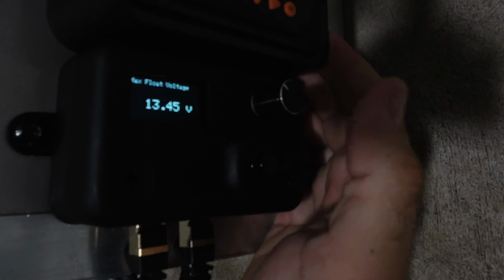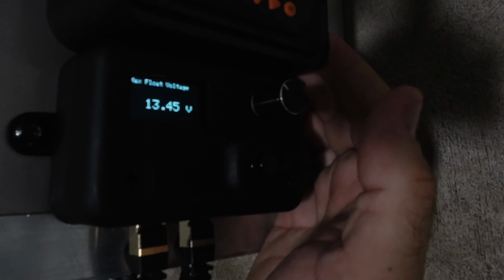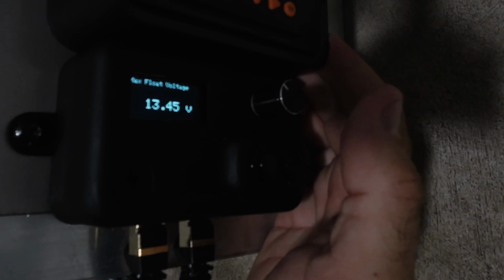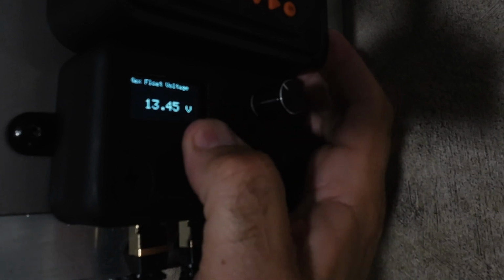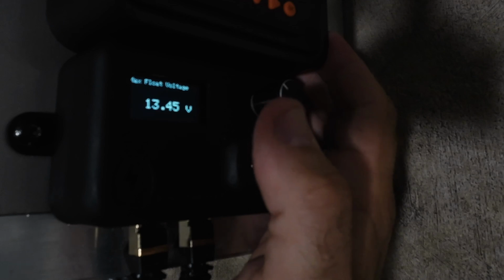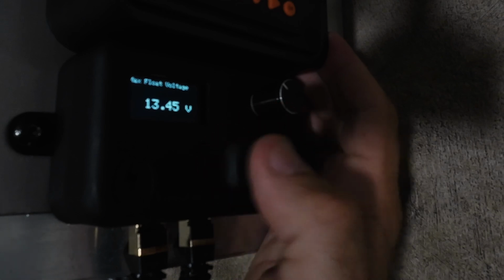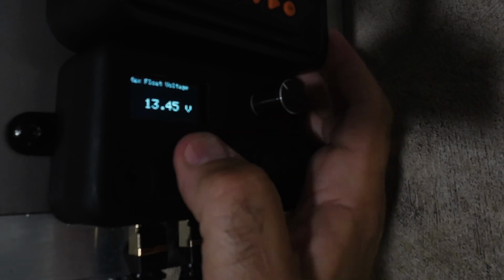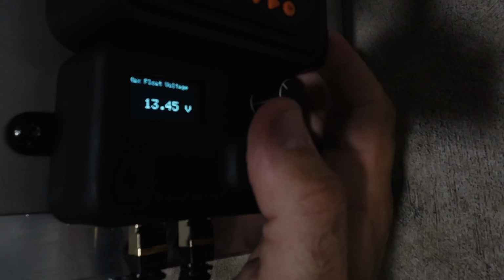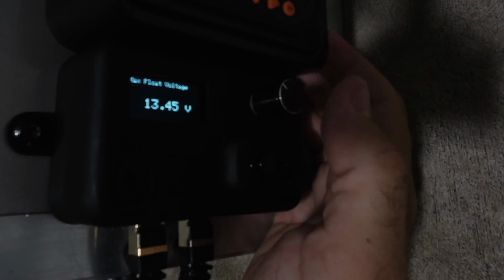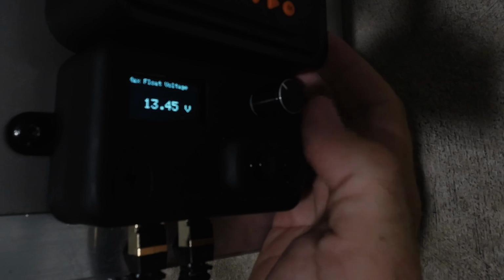The BankManager, when it thinks your battery is fully charged, when it shows an asterisk on the screen, will not put any more current in if you're above this voltage. But once you drop below this voltage, it'll let a little in, a little out, as solar conditions change and loads happen. What that boils down to is if you set your voltage regulators' float below this, I suggest 13.3, it will not click the contactor in and out as much.